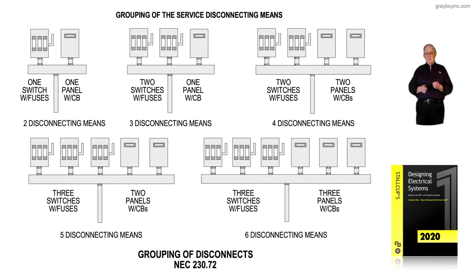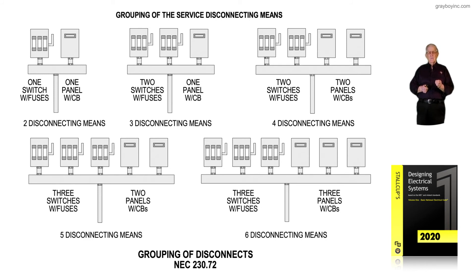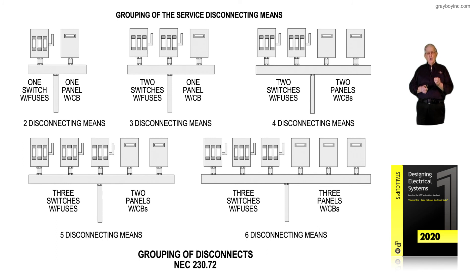Be sure to review 230.80 along with 230.90 and the exceptions listed there as designers or installers, so we know how fuses and breaker mains must be sized in relationship to the conductor sizing. In many cases they're going to be much larger than the ampacity of the conductors. Keep that fully in mind as you design the service using two to six mains.